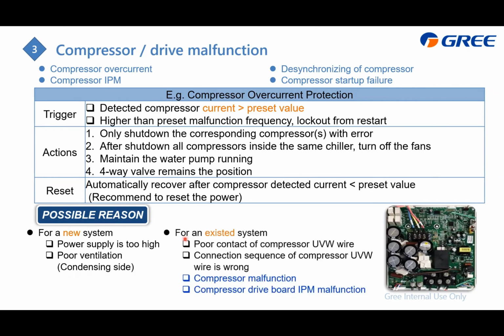And for an existing system, especially when you just repaired the chiller, you need to check whether there is poor contact of the compressor UVW wire. And of course, check the sequence of the UVW. After that, we divide the reason into compressor malfunction or drive malfunction, which is the IPM malfunction.